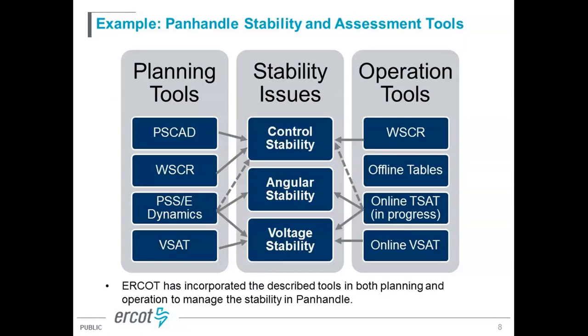On the planning side, because it is a weak grid area, we perform dynamic stability studies. Typically, we use the TSAT tool in the ERCOT region. We also use PSCAD studies to ensure we have enough detail in terms of controllers, VPL, all of this. And we also have VSAT to do the voltage stability assessment. In this case, for the Panhandle, we in ERCOT introduced the weighted short circuit ratio index, for the purpose of having a way to assess and quantify the system strength in the Panhandle regions.